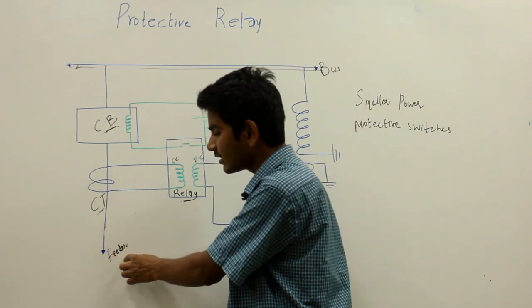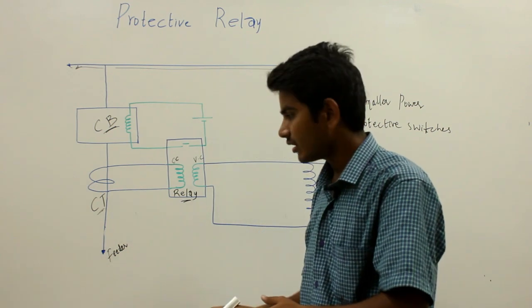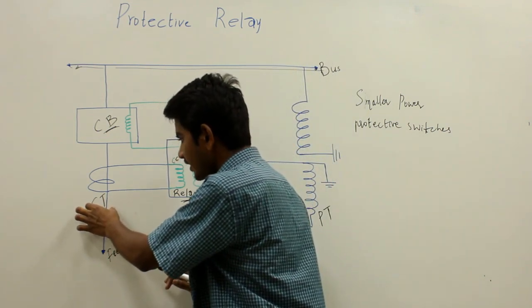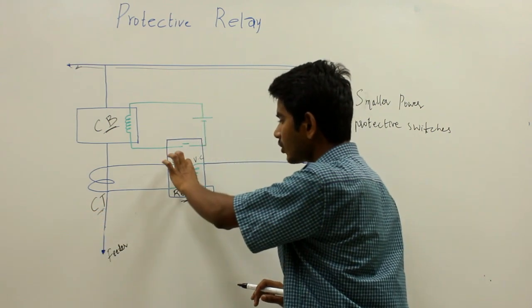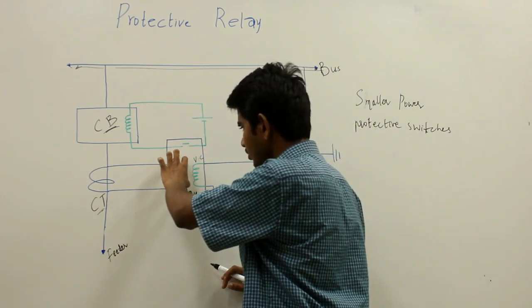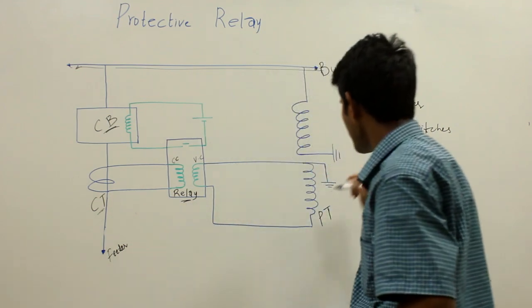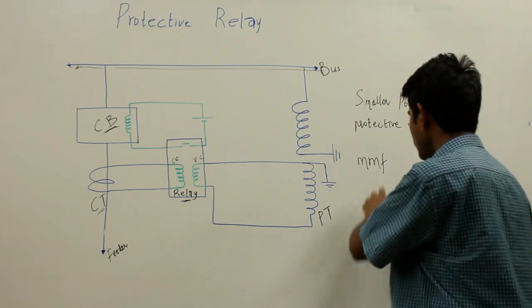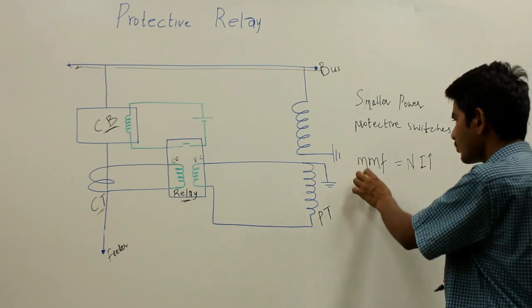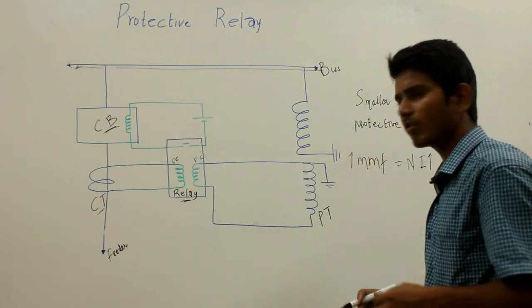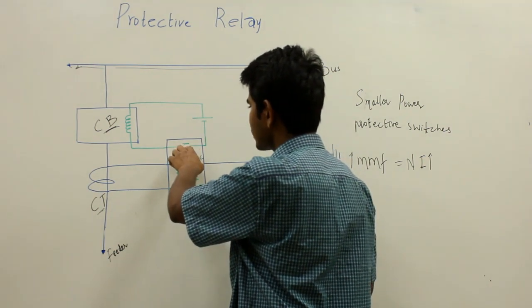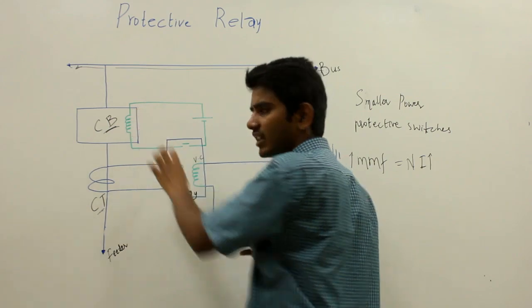Now whenever there is a fault in the feeder circuit, it indicates a high value of current is drawn. The proportionate secondary current of the current transformer will flow through the current coil of the relay. Whenever there is a high current flowing through the current coil, the MMF of the coil increases. We know that MMF of a coil is given by MMF = N × I. As the current increases, the MMF increases and this is sufficient enough to mechanically close the normally open contact of the DC trip coil circuit.